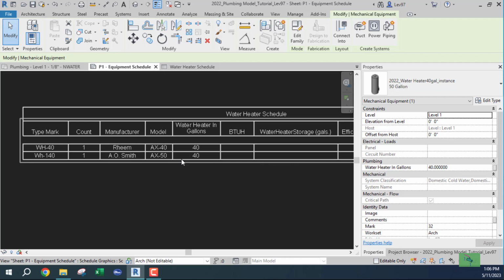So if you're having problems, you've got to get down to the lowest denominator of Revit. If you see any kind of warning, you have to look at it and find out what Revit is actually doing. Because otherwise, you could get caught in a cobweb of things. I mean, if you're way down the line on a project and you're wondering why you're getting these duplicate type marks, or you're wondering why your equipment is not showing up on your equipment schedule.